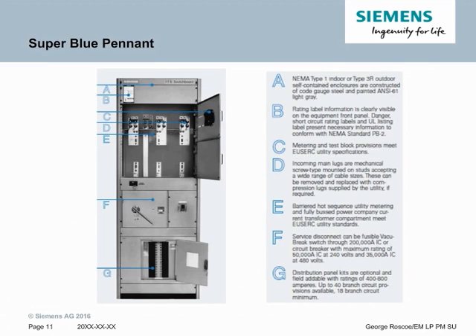The first stock switchboard we will talk about is the Super Blue Pennant. It is a NEMA 1 or Type 3R outdoor enclosure and it is EUSERC-approved with the metering and test block design. The incoming main lugs are mechanical screw type that accept a wide variety of cable sizes and they can be removed or replaced with compression lugs for the utility if required. The Super Blue Pennant is hot sequence, as EUSERC utilities are hot sequence boards. The service disconnect will be right below the hot sequence utility metering compartment, either in the form of a vacuum break switch or a circuit breaker. Super Blue Pennant with vacuum break switches are rated to 200k IC, or the circuit breakers are a maximum of 50k IC at 240 volts and 35k IC at 480 volts. Additionally below will be a small distribution panel, the size of which is dependent on the ampacity and the type of main you use.